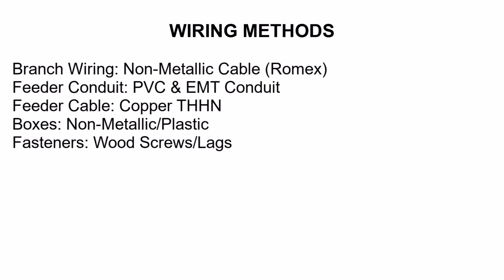Wiring methods: we're going to use non-metallic cable, also known as Romex, for branch wiring. Feeder conduit is PVC underground and then EMT risers. Feeder cable is going to be copper THHN. Boxes are going to be non-metallic plastic, and fasteners with the wood studs are going to be wood screws and lags.